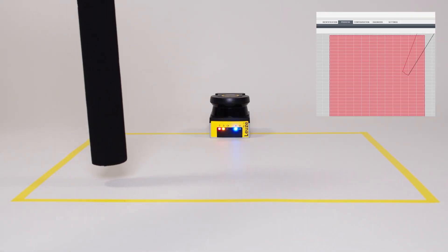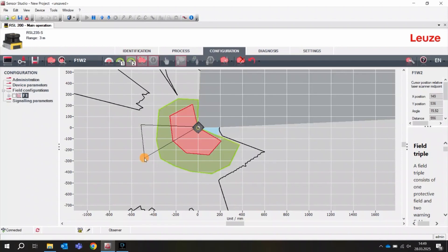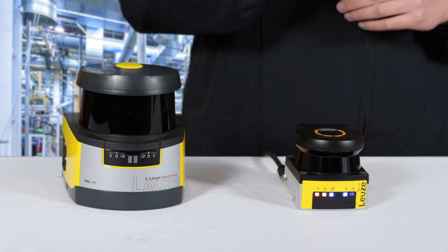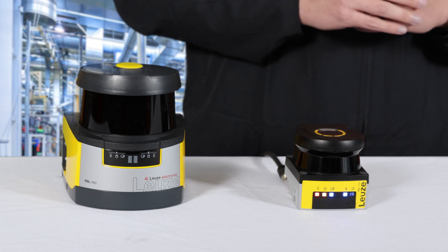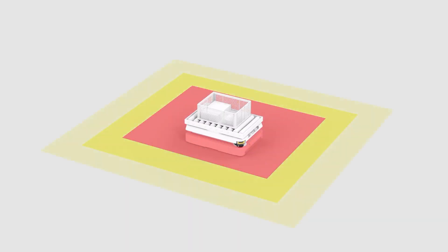The RSL 200 and its big brother, the RSL 400, both use the same intuitive, easy to navigate software. The RSL 200 is optimized for tight precision applications, offering an even wider 270 degree field of view, a three meter protective field, and a refresh rate of up to 50 milliseconds, making it one of the most responsive scanners available today.